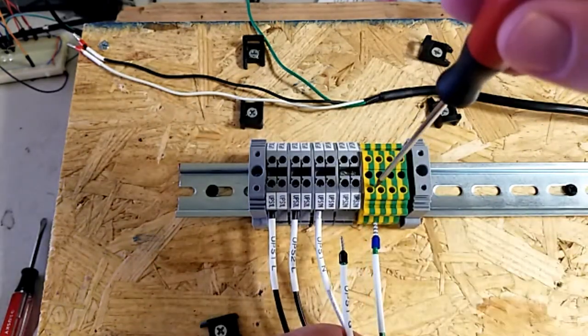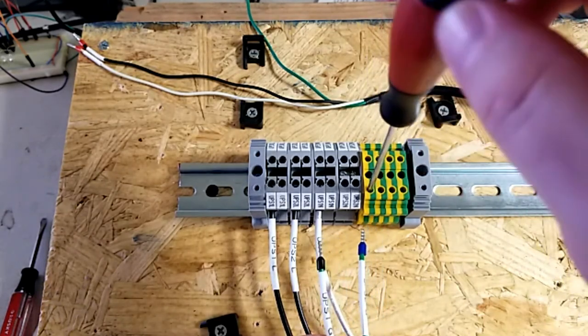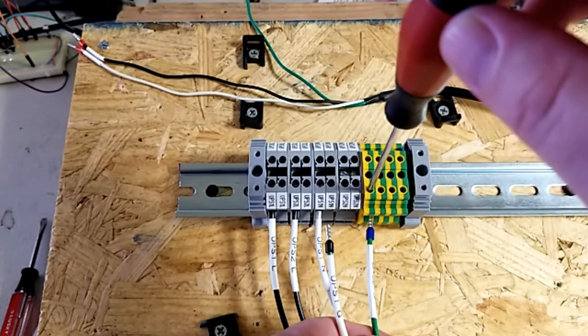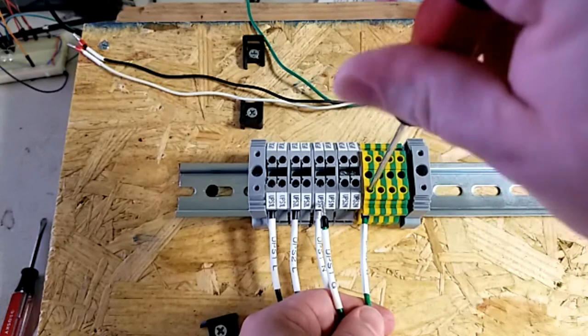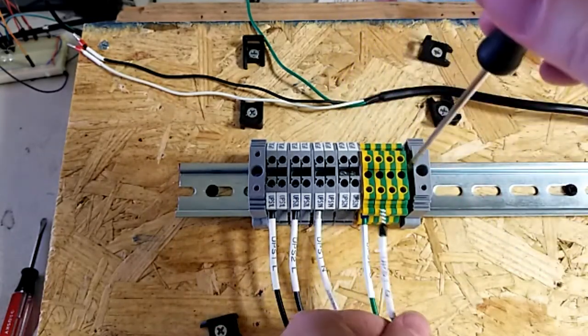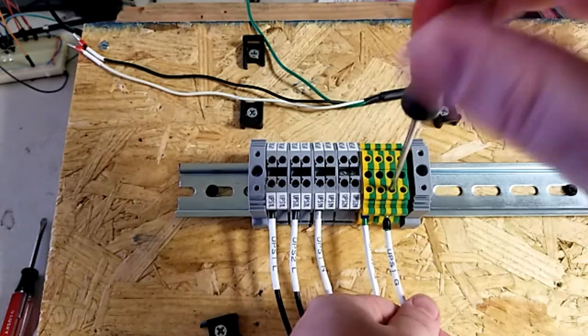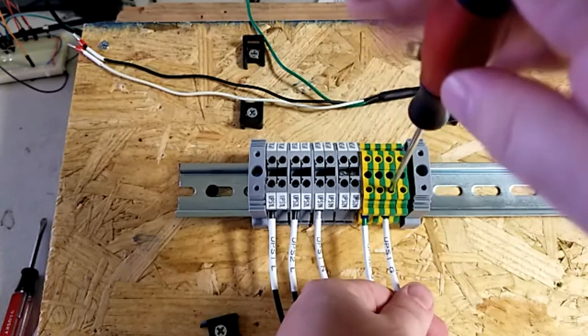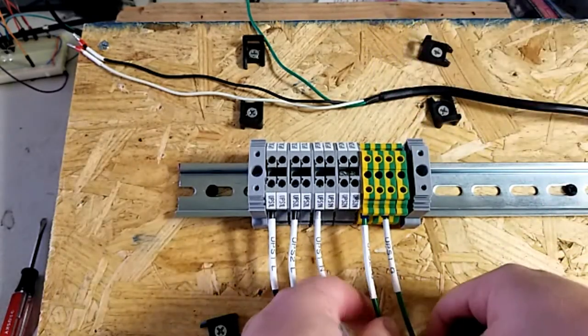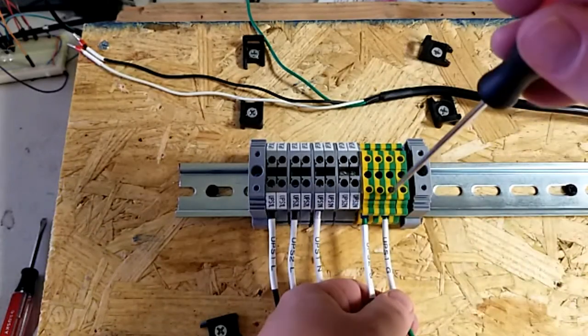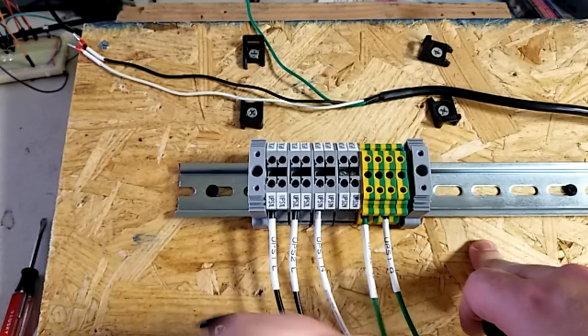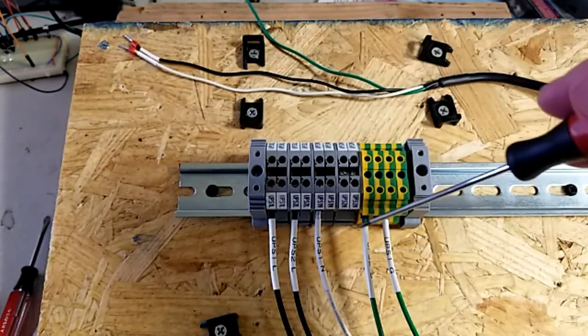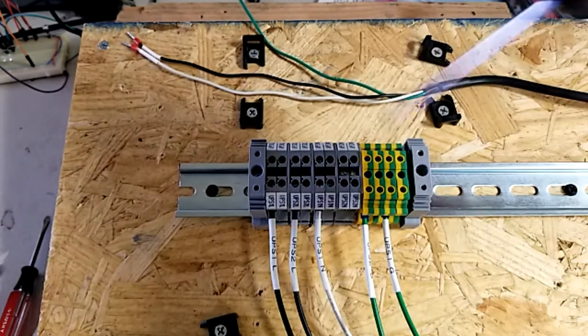And again, just like the other terminals, you go into the small hole at the top or bottom for whatever side you're connecting. You can loosen it up a little bit, slide your wire in, hold it firmly, and then tighten it down. And once again, it does not matter what hole you go into as long as all of your ground wires are in firm. Whenever you get a wire tight, it should be seated as deep as it can be in there. And then once tightened down, give it a little tug test, make sure it's snug in there. So, replace all the bottom and all of the top ground wires.